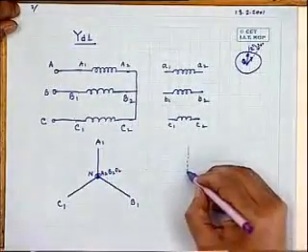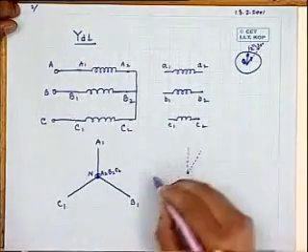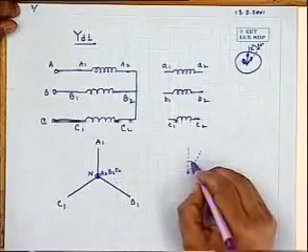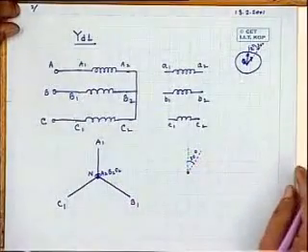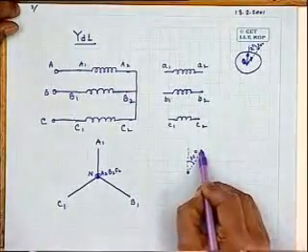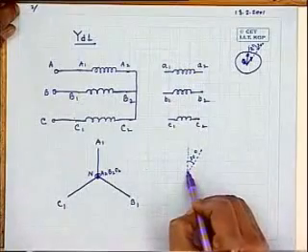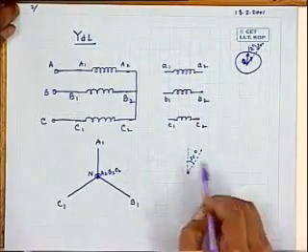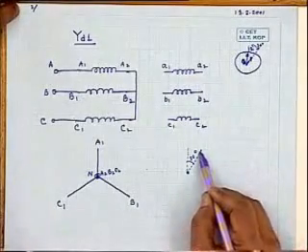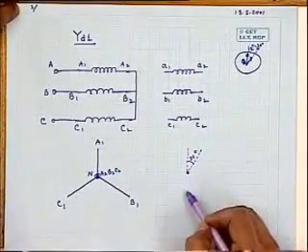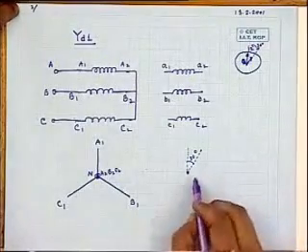So what I will do, here I will first draw a line parallel to the A phase voltage. Now draw a line 30 degrees lagging this one. That is, this point should be my A phase voltage of the secondary with respect to this artificial neutral. The triangle I have not completed yet. Once this point is fixed, the other sides get fixed because it will be a balanced three-phase voltage.